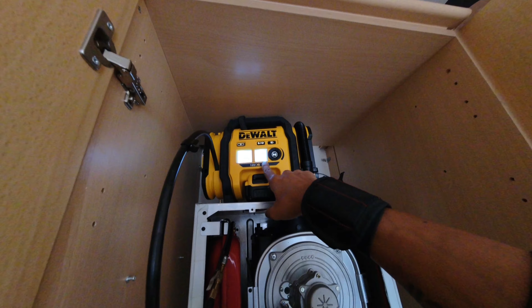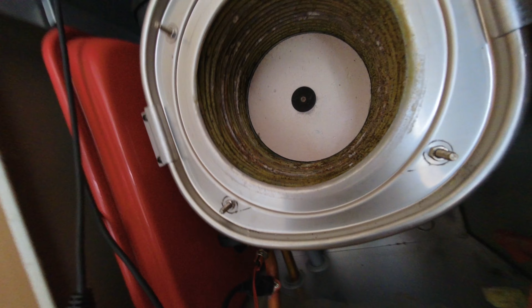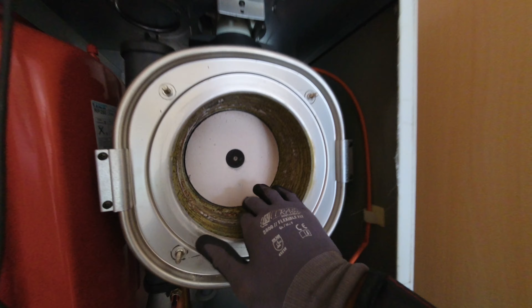Okay, so I've got the burner out. Electrodes and the rectification don't look in too bad nick. The burner itself is fairly clean as well. Heat exchanger, that has never been opened up, but for a boiler which is about 15 years old, that's actually not so bad. You've got a little bit of dusting on there, so I'm going to get the brush, give that a clean, and then make this all nice and shiny as much as we can do without obviously disturbing the actual heat exchanger. So we'll give this a clean, put it all back together.